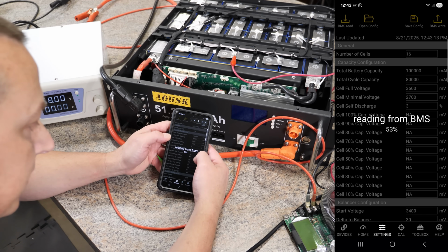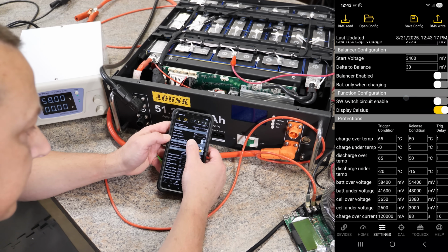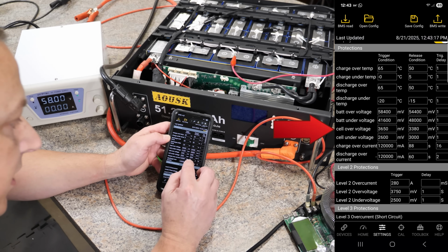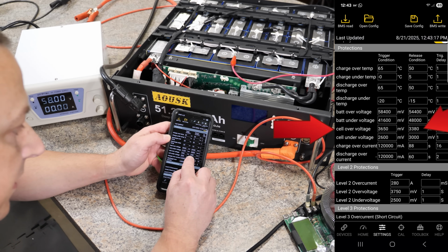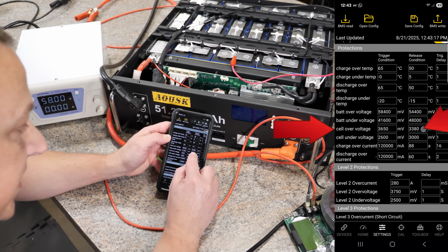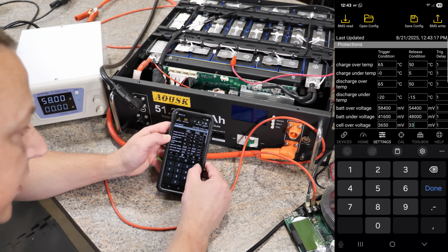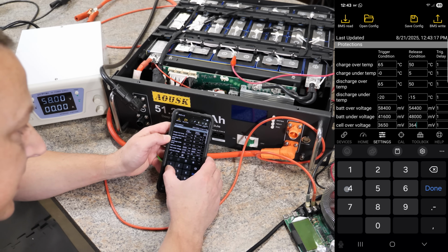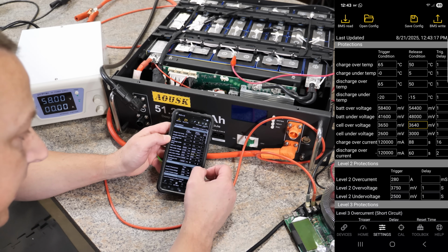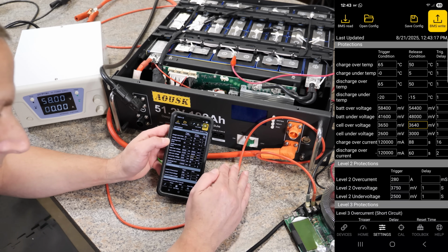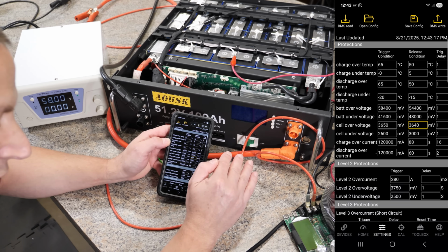So you won't have to keep resetting the BMS and reconnecting with the app, which is what I usually do, I'll go down to the cell overvoltage release setting. Right now they've got it set for 3.380 volts. I'll typically change that to 3.640 and hit done.